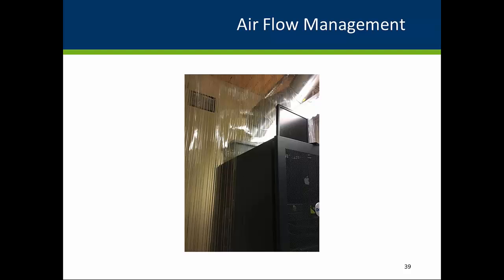Plastic drapes were installed to create a contained hot aisle where the exhaust fan could remove the heated air. This measure resulted in inlet rack temperatures in the range of 75 to 78 degrees. The cost of the plastic was less than $100. The site was planning on installing dedicated cooling, and this measure avoided HVAC work estimated to be in the tens of thousands of dollars. This also raised the possibility of putting the exhausted waste heat to more productive use elsewhere in the building.